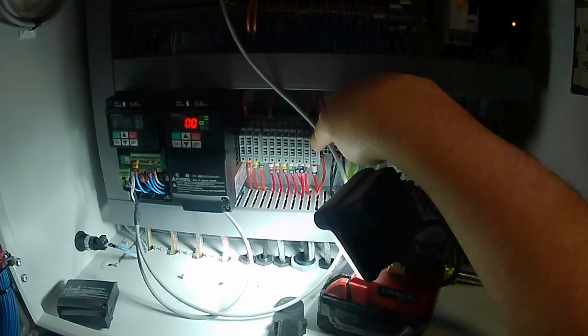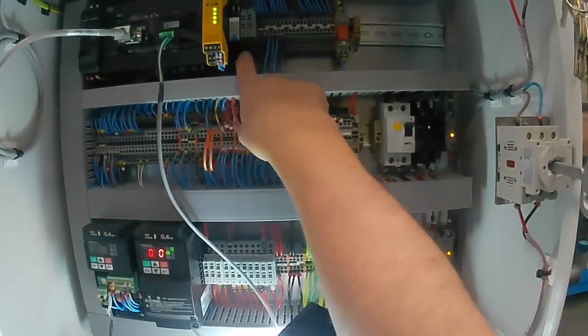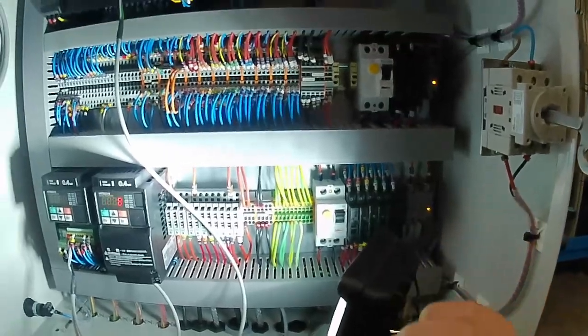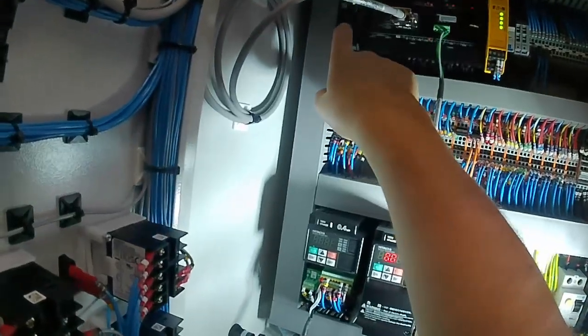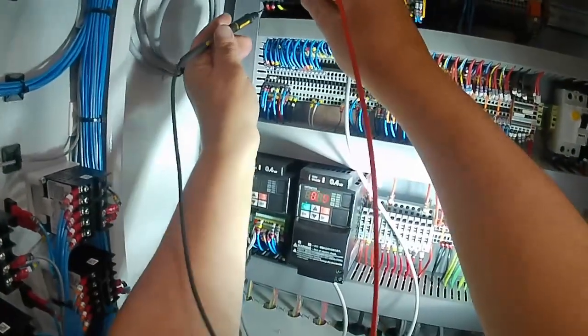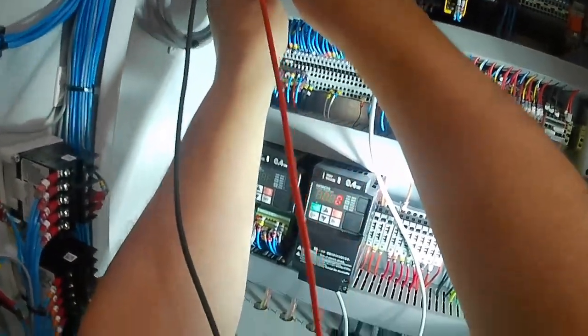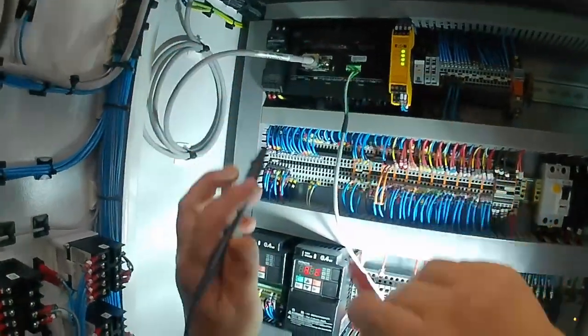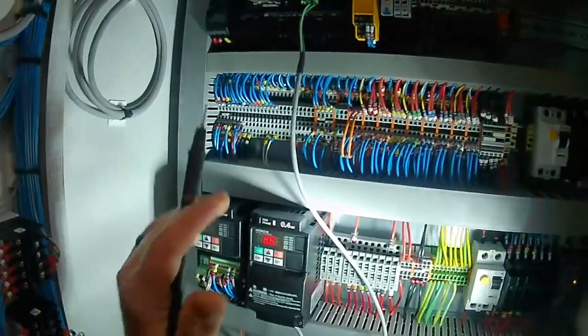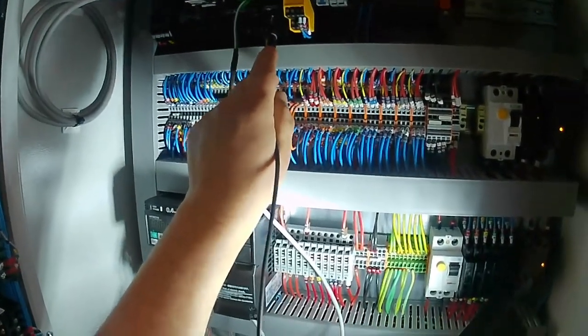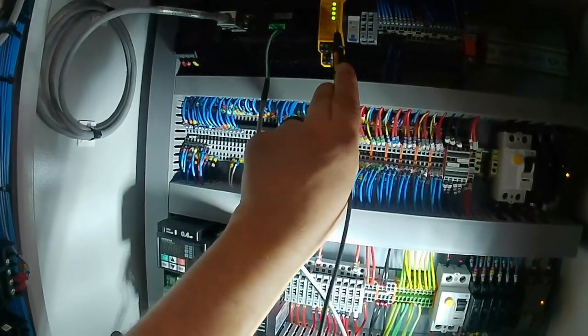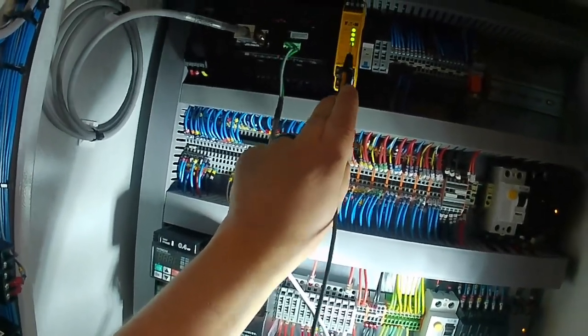I think these are fuses. Yeah, this is a fuse block right here, and there's fuses right there. But usually in the control panels, what is this? A power supply? Power supply. Let me see if we got some voltage on this power supply. 116, and I'm assuming it's 24 volts out. Yeah, 24 volts out, but that's probably feeding the PLC. And then we got our safety, which on our safety K1 and K2 are met.